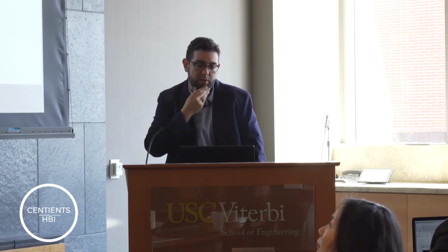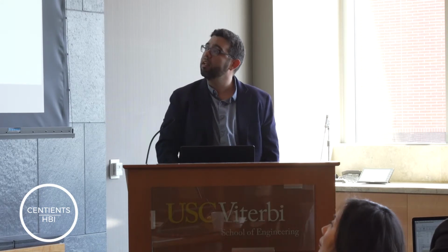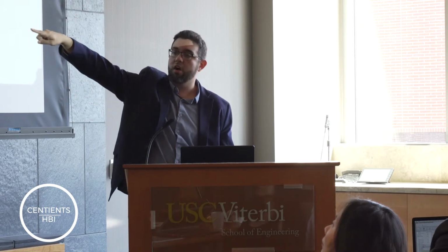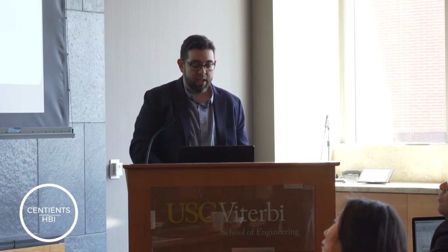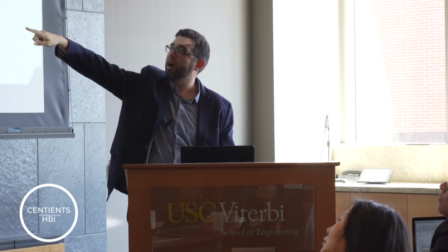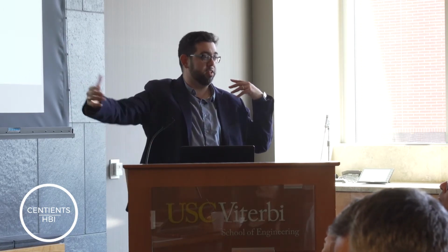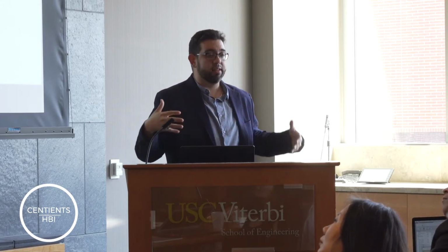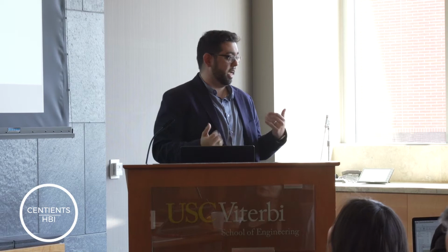An interesting thing that we found post SBS is when you run correlations, you get this interesting spatial property where things that are very highly correlated post SBS analysis are sensors that are observing similar phenomena in a similar space. So this is just showing how, if you change the threshold on the correlation coefficient, the scope of sensors that are included in the set increases. And so we leverage that in order to model canonical behavior and sensors that are activated in concert in order to support local building activity.